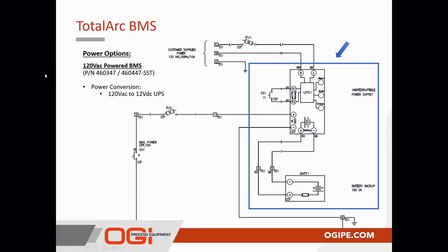As I said, it has an onboard, in this case, 2.6 amp hour battery that's being charged by the UPS system from the 120 volt supply. And whenever that would be lost, we would have up to 10 hours of backup available.